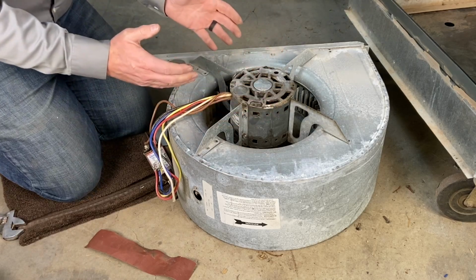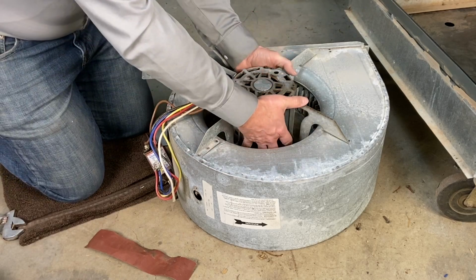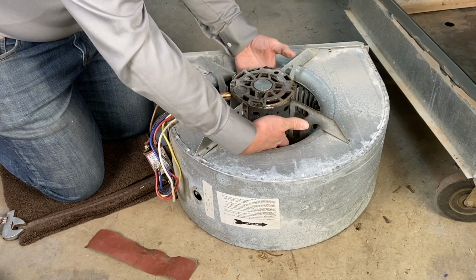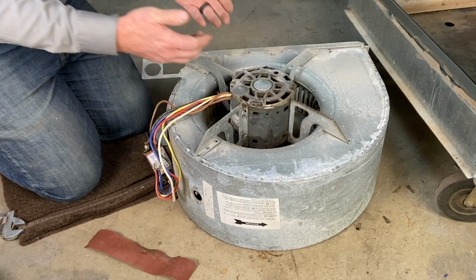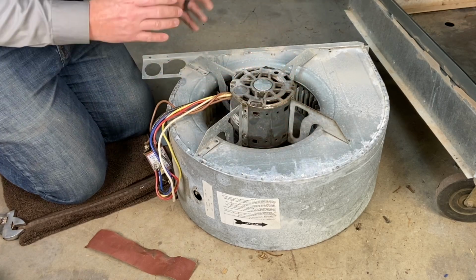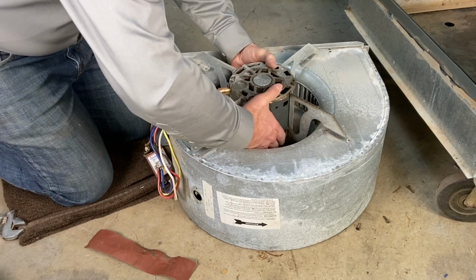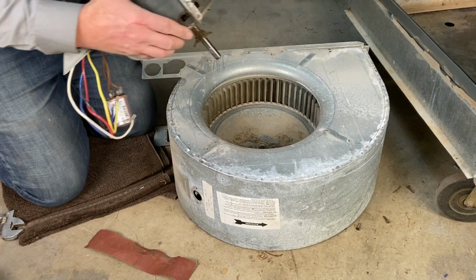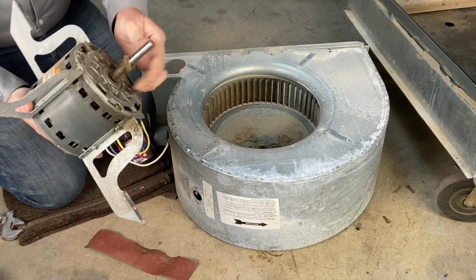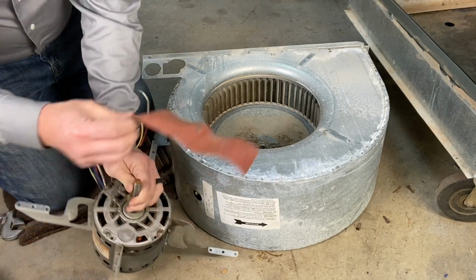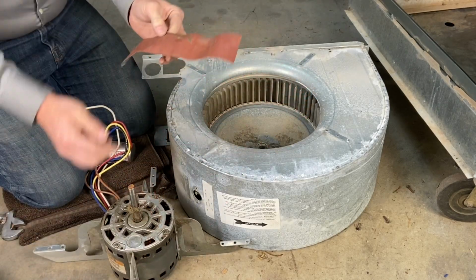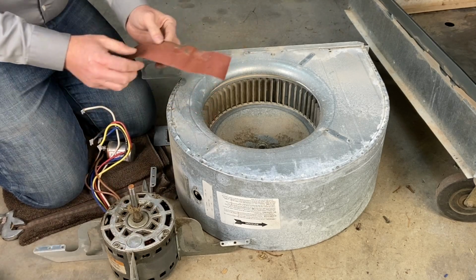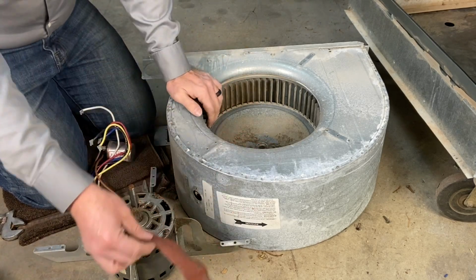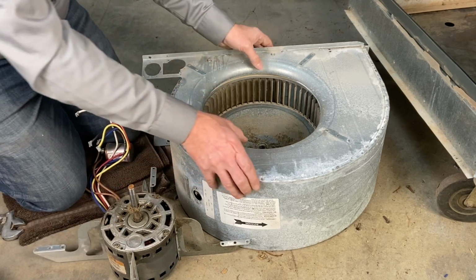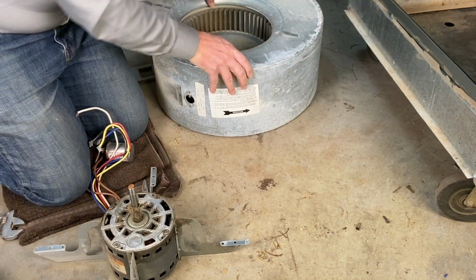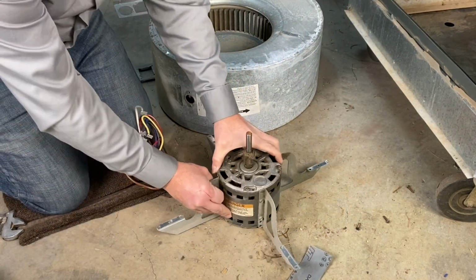Now when we pull this motor out, I'm going to reach down and grab the motor itself, use the sides as leverage, I'm going to pull this motor. And ideally it will come right up without having to use any kind of puller. So here we go. Perfect. The reason it happens like that, it's not by accident. It's because we used our sand cloth, we sanded this shaft down, and we also used that little bit of oil in there. So that allows us to get this housing out. Now if we move our blower out of the way, let's take a look at this motor.